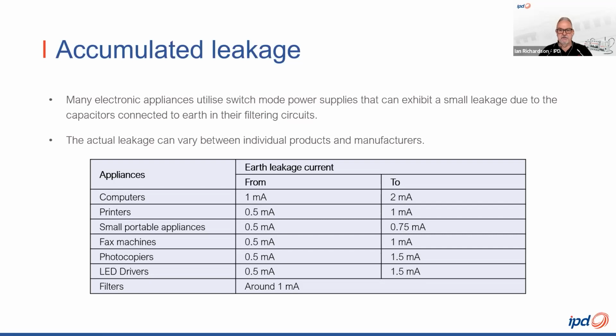Now, if we start adding on a few monitors and some desktop printers, and they've all got a similar sort of issue as far as leakage goes, we can see it starts to make sense that this accumulation of leakages across those loads is the reason that the RCD could trip. I think the table helps to understand the hidden nature of leakages in standard equipment and points us to identifying possible reasons for the so-called nuisance tripping.